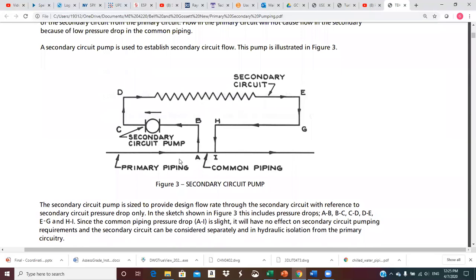For example, if this were a huge pump pumping across campus needing lots of pressure, and that pressure differential from the primary is what's driving flow through the secondary circuit, that would force control valves to operate against a much larger head. In a primary-secondary arrangement, the head that control valves in the secondary operate against is just provided by the secondary pump, which is a small, almost insignificant pump compared to your large distribution pumps.